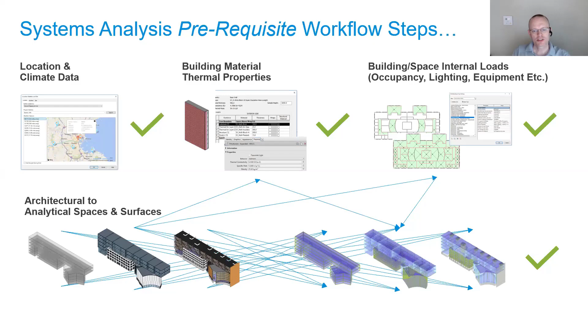Once those optional steps are done, you can go straight in and run a systems analysis, which provides what we call an ideal loads calculation. In other words, it tells you how much heating and cooling each individual space needs, the maximum, and then the total for the building. But it won't account for the energy it takes to deliver that heating and cooling, because you haven't defined the mechanical system.